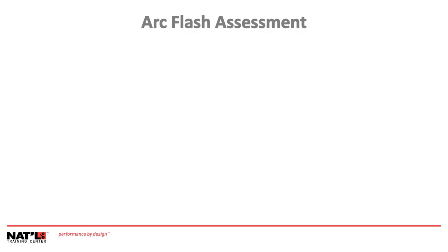Arc flash assessments. Arc flash risk assessments shall be done for all routine tasks performed in the cell line working zone. The results of the arc flash risk assessment shall be used in training employees in job procedures that minimize the possibility of arc flash hazards.